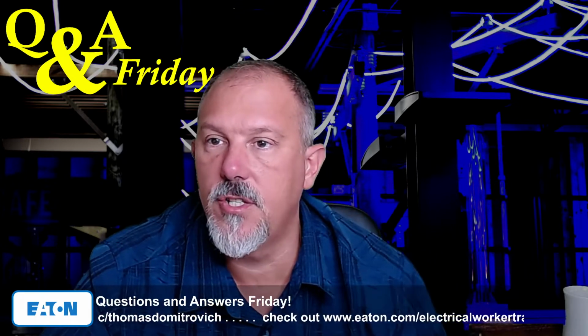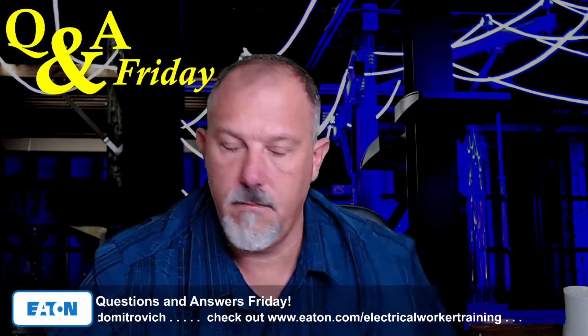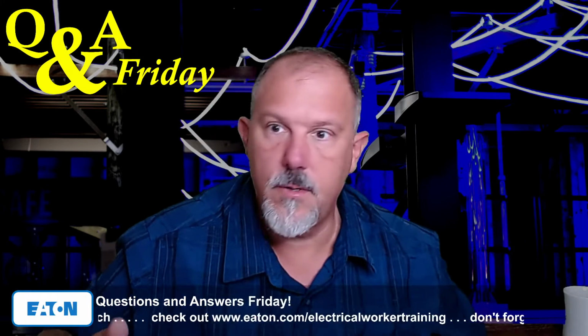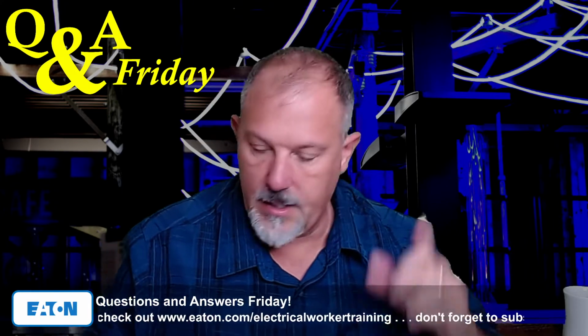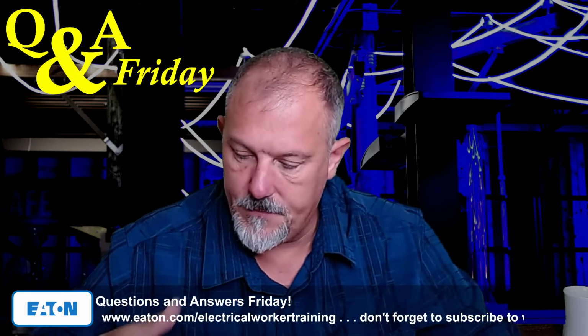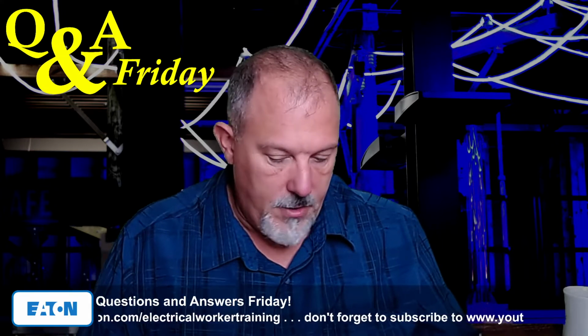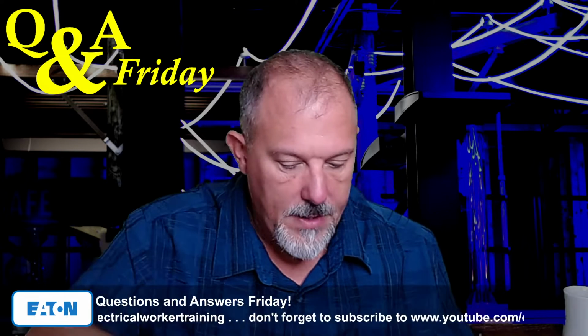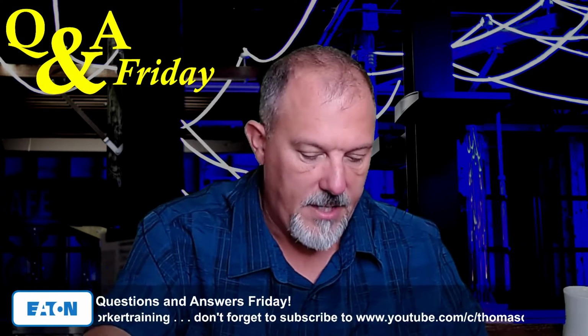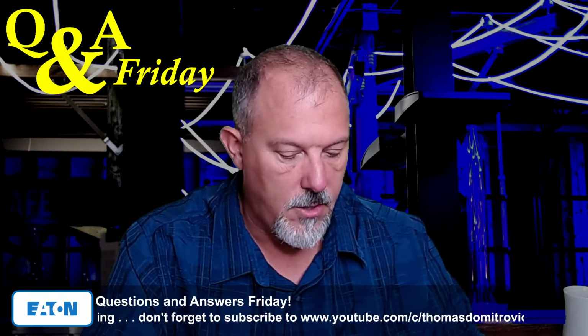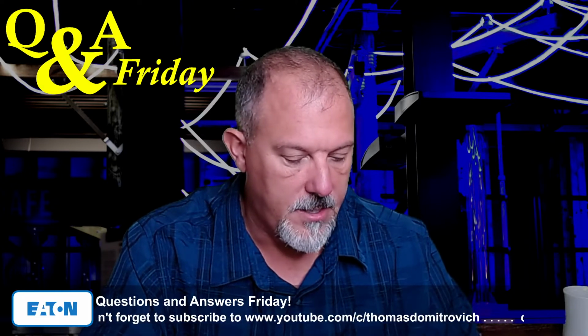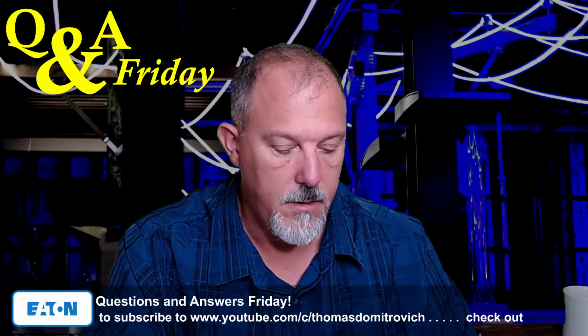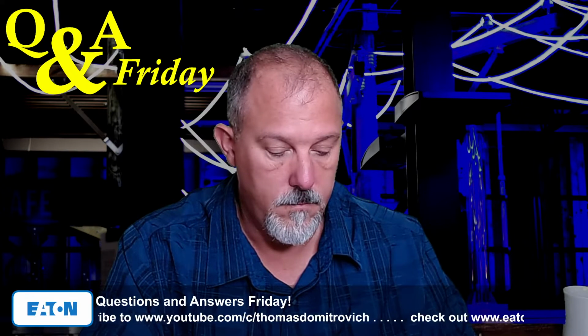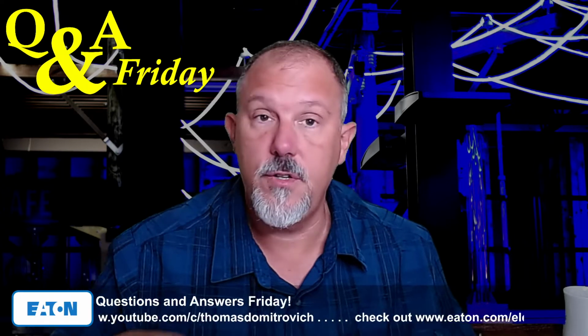L says, on a circuit breaker that provides overcurrent protection. Okay, so on a circuit breaker, so let's see, he's still arguing 240.87, where the highest continuous current trip setting for which the actual overcurrent device installed in a circuit breaker is rated or can be adjusted is 1200 amps or higher. Right. So put it this way, that language is in 230.95.